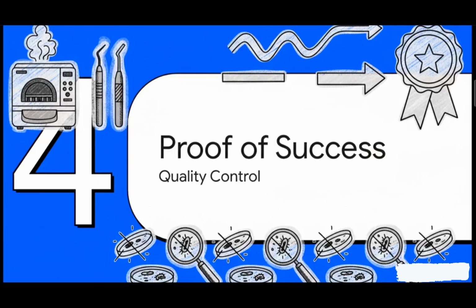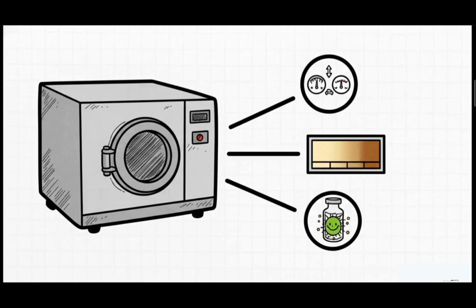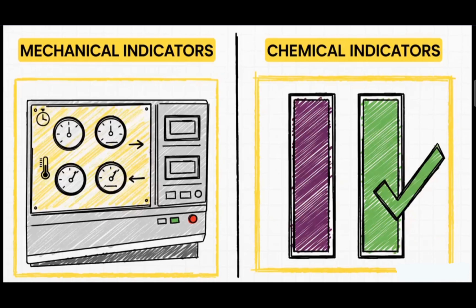And that's where this final, crucial step comes in: quality control. They don't just assume it worked, they prove it. Every single time. There's actually a 3-layered system of checks and balances to make sure every single sterilization cycle was a success. These are the mechanical, the chemical, and the biological indicators. Okay, so first up, you have the mechanical indicators. These are literally the gauges on the machine itself, just confirming that it hit the right time, temperature, and pressure. Then you've got chemical indicators. These are special strips inside or outside the packages that change color, just like you see here, but only if the right sterilizing conditions were actually met. These are your first 2 lines of defense.